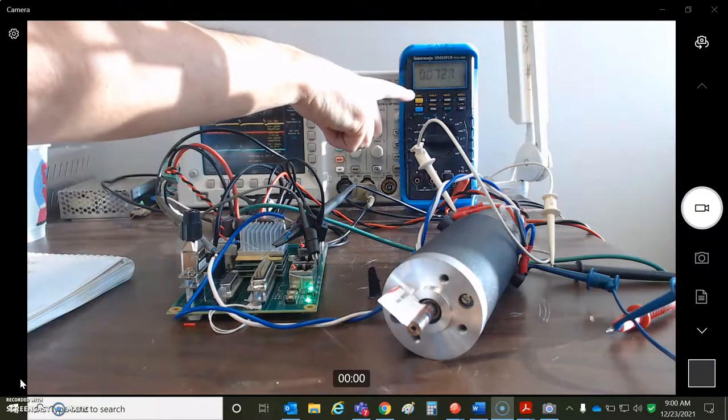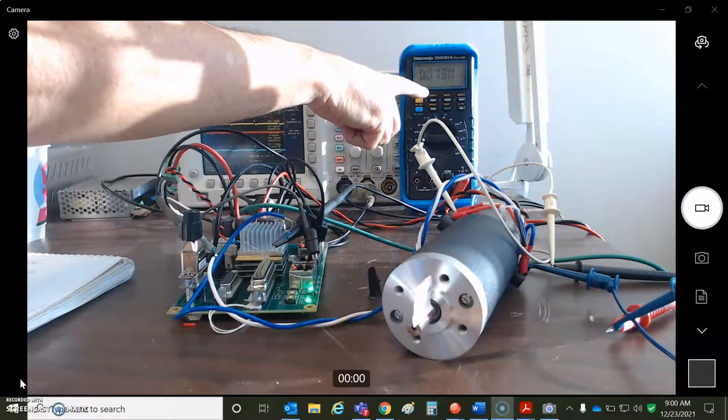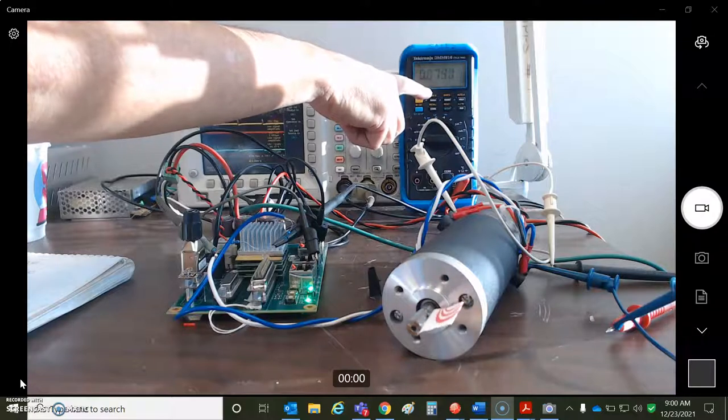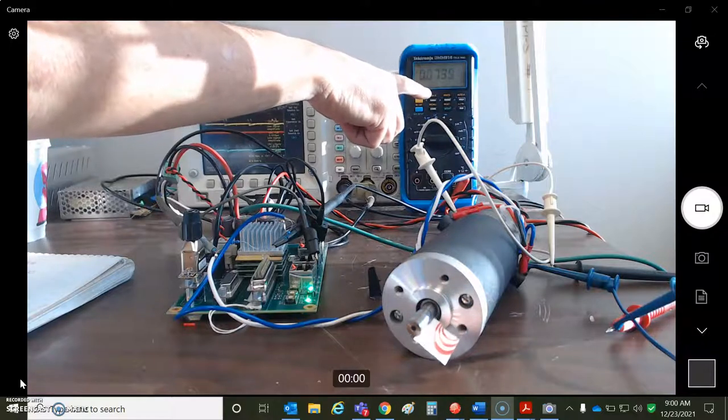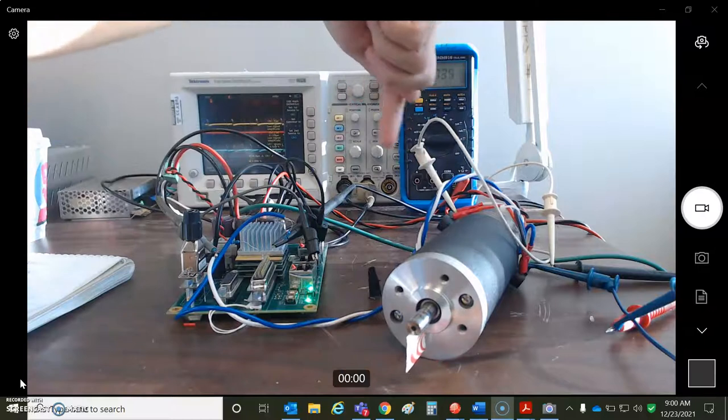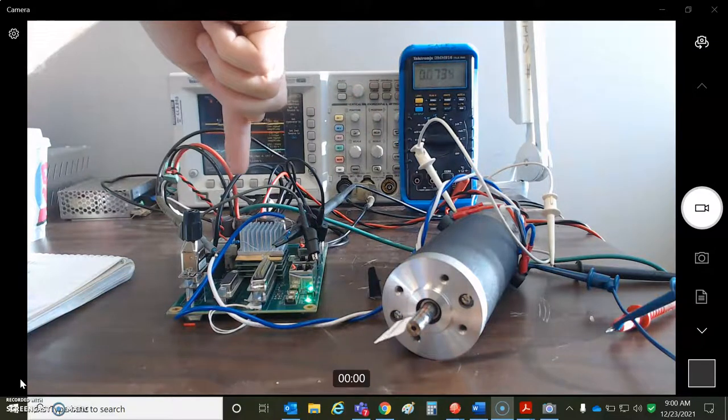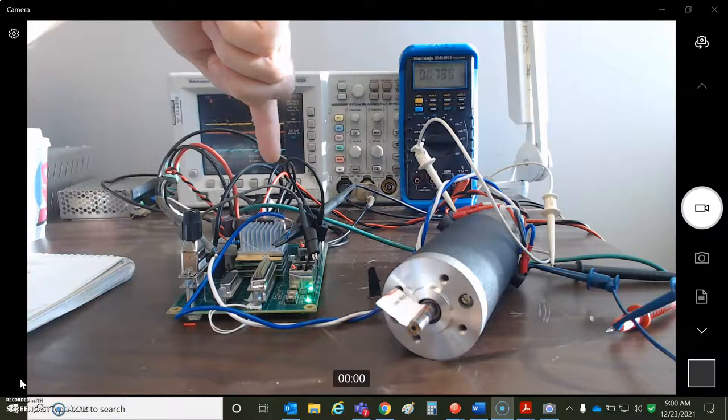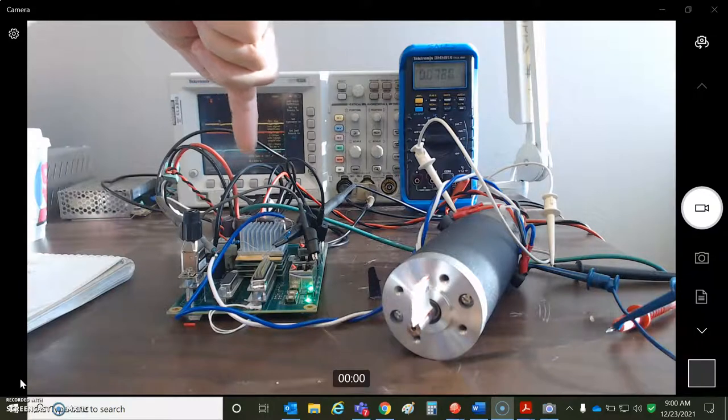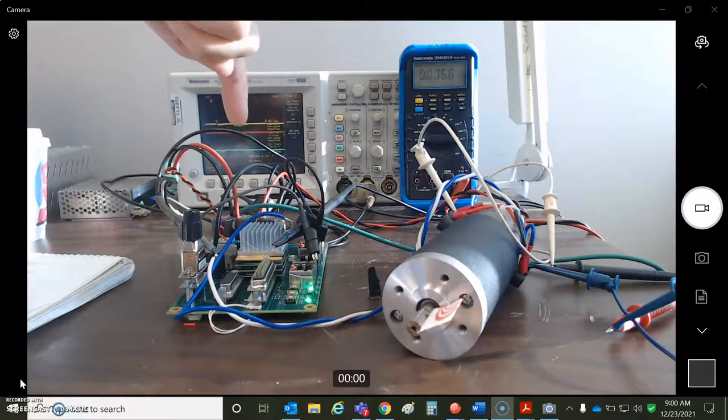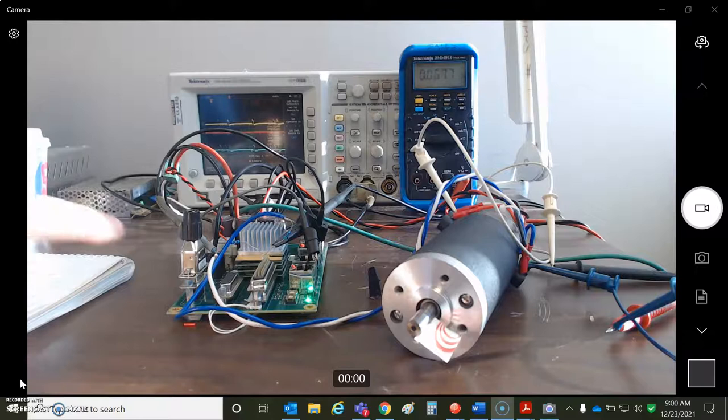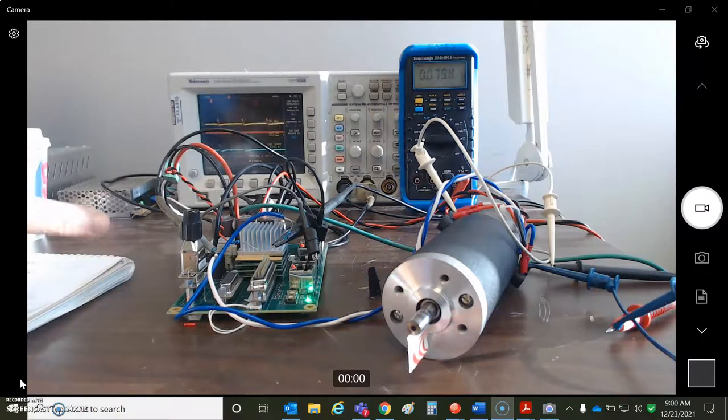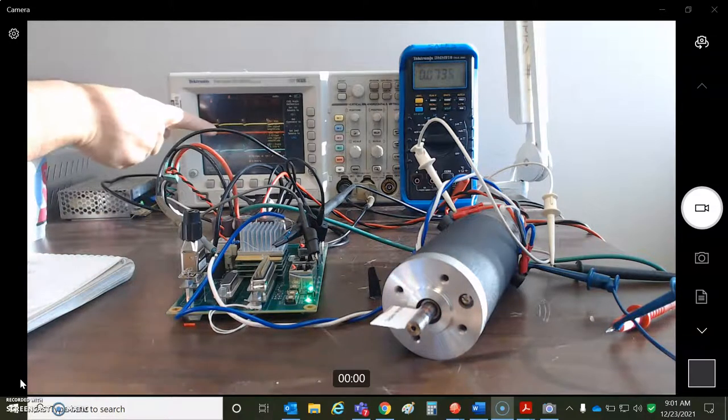You can see on the voltmeter, you got about 73 millivolts here of offset measured at the tachometer. Divide by three, you're going to get like 25 millivolts of offset at the analog input. Because it's an analog circuit, it has not been calibrated.